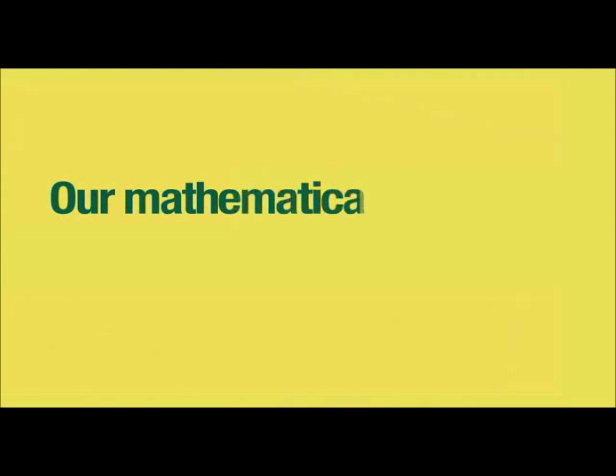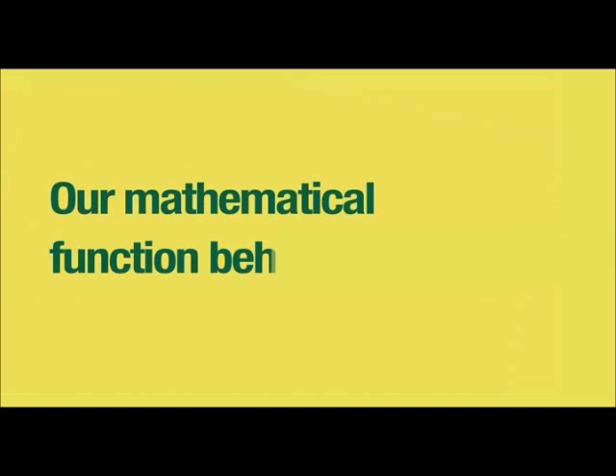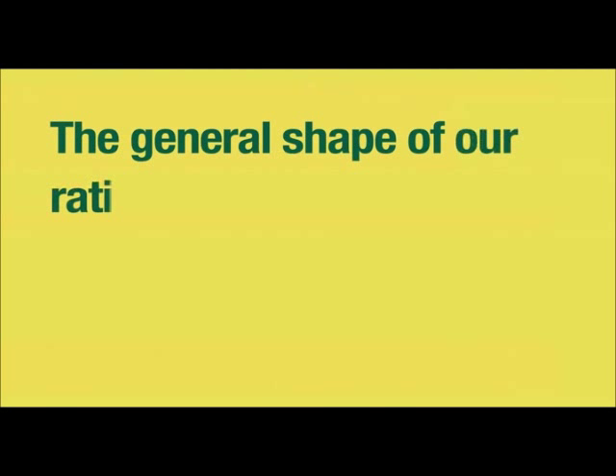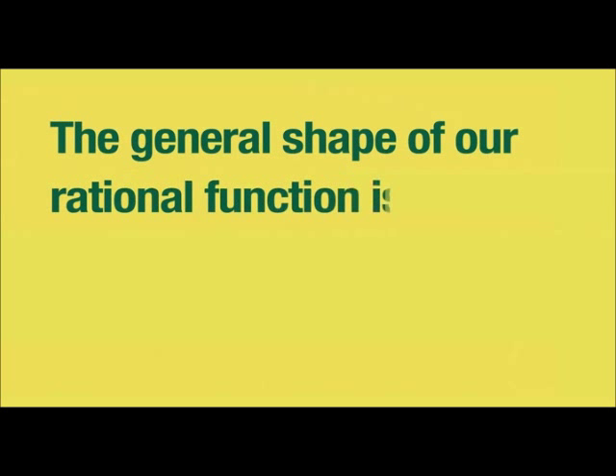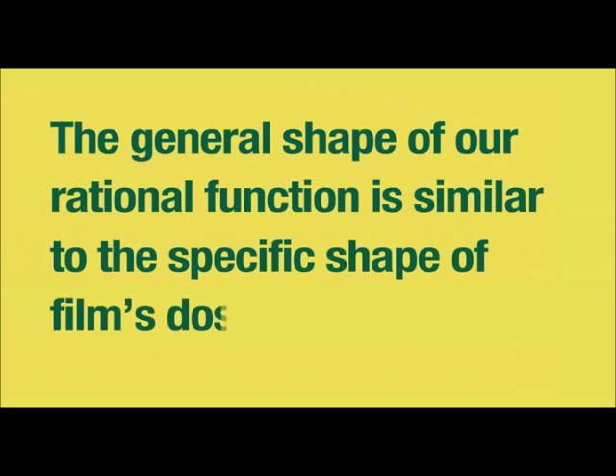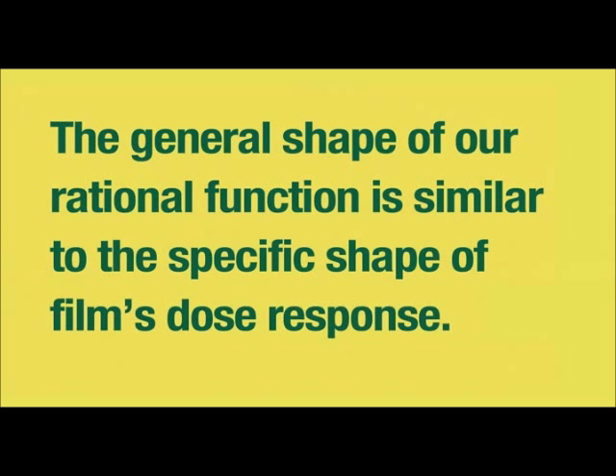By contrast, FilmQA Pro 3.0 fits the data with a rational function that behaves just like film. Film gets darker and darker the more it's exposed, and the transmission asymptotes to almost constant value at high dose. So because the general shape of our rational function is similar to the specific shape of the film's dose response, you need fewer data points to make a match.